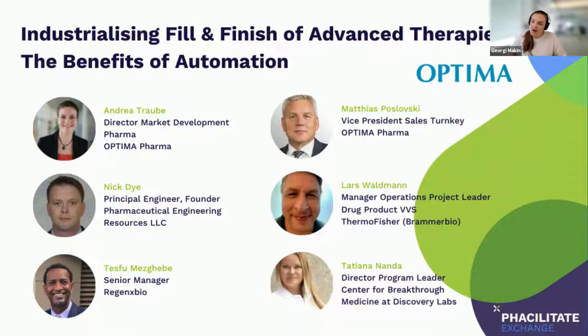More questions for Matthias: do you have the ability to return VHP back into the clean room, not hard-ducted? You can take the isolated air from the room back into the room during the VHP process. There are two capabilities: one is going over the ceiling or roof with the VHP during aeration, or you have a catalytic converter — highly efficient — before you bring back the air into the room. Both things are possible depending on your preference. On such a small machine, it's very common to take air from the room back to the room, which means if you have an HVAC, it's extremely small.